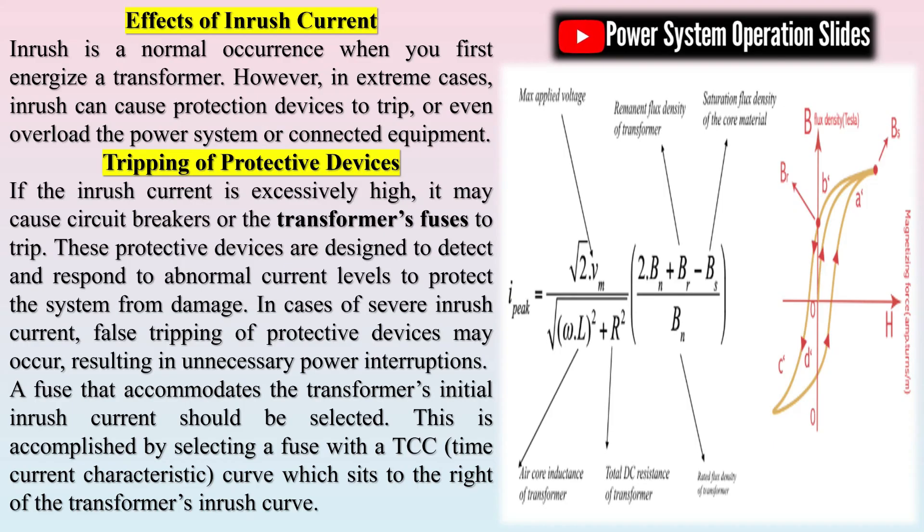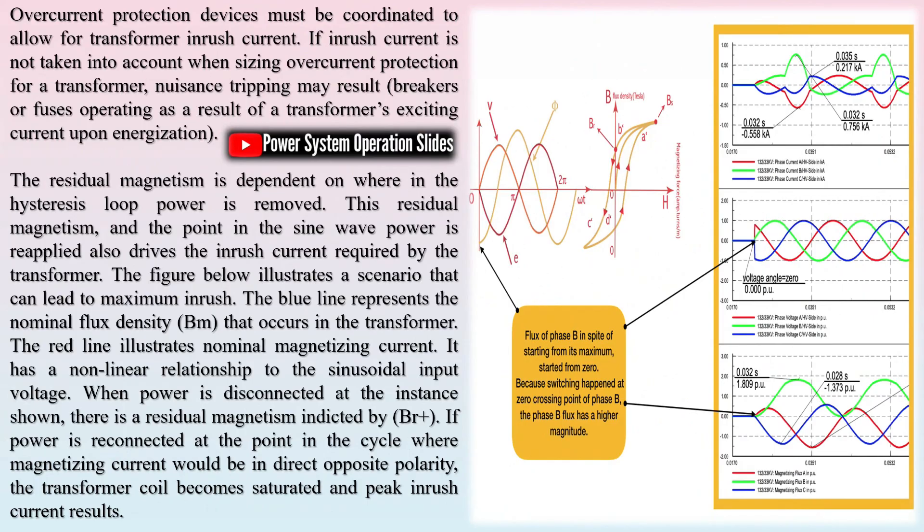Inrush current calculations depend on several factors, such as the saturation characteristics of the transformer core, the waveform of the supply voltage, and the specific transformer design. Calculating transformer inrush current is a complex process that involves several interrelated factors. The transformer core exhibits a non-linear behavior governed by its BH magnetic curve.